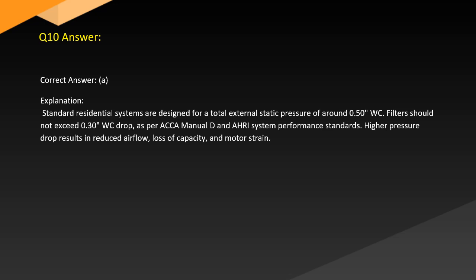Answer. Correct answer: A. Explanation: Standard residential systems are designed for a total external static pressure of around 0.50. Filters should not exceed 0.30, as per the ACCA manual and the AHRI system performance standards. Higher pressure drop results in reduced airflow, loss of capacity and motor strain.